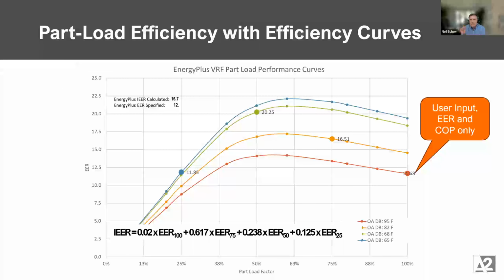In a model, you're stuck with a set of performance curves. Over studying systems in the field, we found these to be somewhat conservative. They're reasonably efficient. They're not as efficient as you might see in the relationship of an EER to an IEER product. You can definitely buy products that are higher. But as a modeler, you just plug in that one efficiency. At 100%, I do 11.7 EER. And these curves, which most modeling software will use, the curves from the Florida Solar Energy Center, give you that part load efficiency. So they say at half speed, at a different temperature, I can get a 20 EER out of the product instead of 11.7.